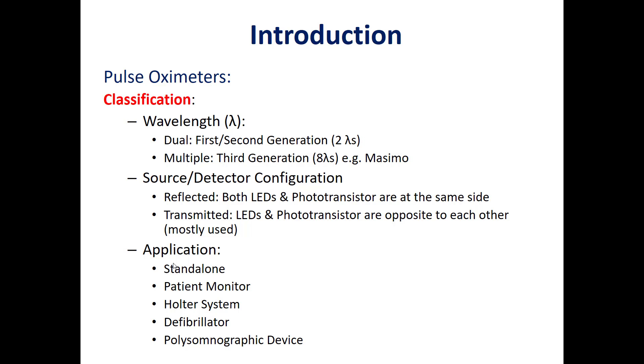We measure the SpO2 or blood oxygen saturation along with other parameters. This is available in patient monitors and vital signs monitors. We can also have a pulse oximeter as a Holter system, used to record oxygen saturation over a long period, like 24 hours or more — one, two, or three days depending on the application.